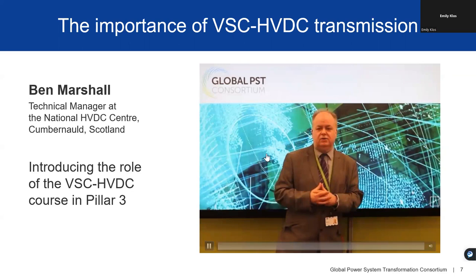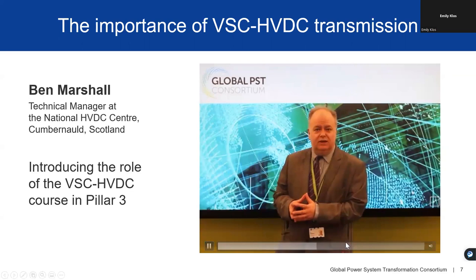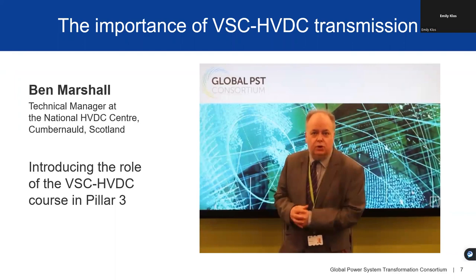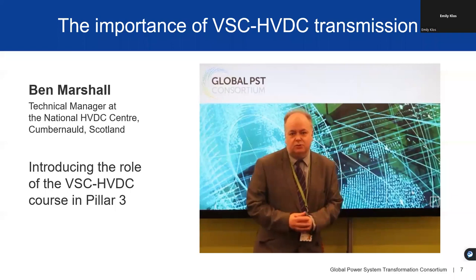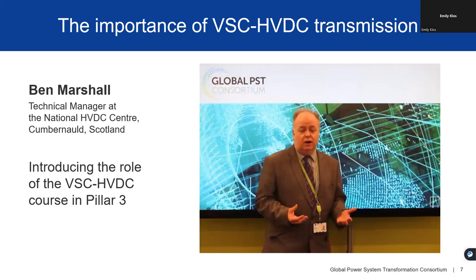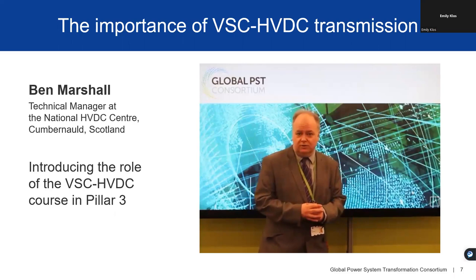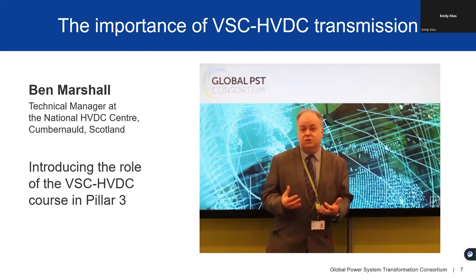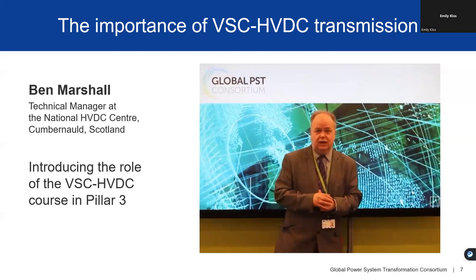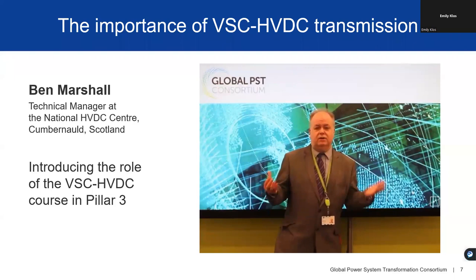MMC technology, as a subset of VSC — voltage source converter — technology, is the critical technology enabling large-scale offshore HVDC implementation. There are a number of projects already, both in Europe and China, with more coming in the US, which are deploying HVDC as the principal means of transmission between the offshore environment and the onshore system. Within GB, we're expected to see our offshore capacity grow from around 10 gigawatts today to over 40 gigawatts by 2030 and over 80 gigawatts by 2050. We need to understand what these converters contribute to the robustness of the grid and provide security for increasingly offshore, disconnected AC systems which have no inherent inertia or stiff voltage sources of their own.